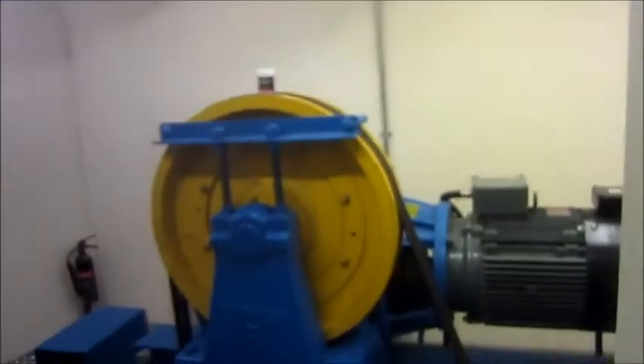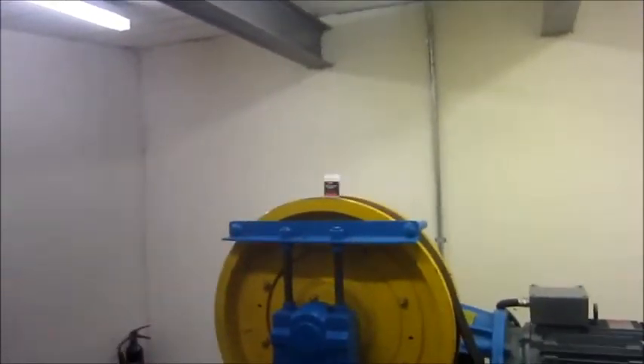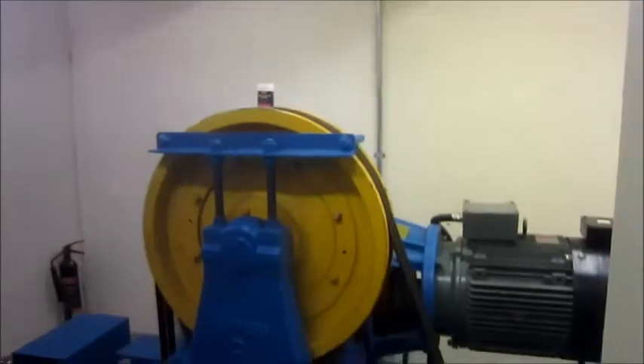If you ever notice, sometimes you get in lifts and it will drop before it goes up. What's happening is it's lifting the brake but it's not got the control quite right, so it drops a little bit. They call it rollback. You'll get that on lifts that don't have gearboxes, typically, because they don't have that friction in the gearbox to hold it for that moment before it pulls away. So in the industry, there's quite a big thing about how to prevent rollback.